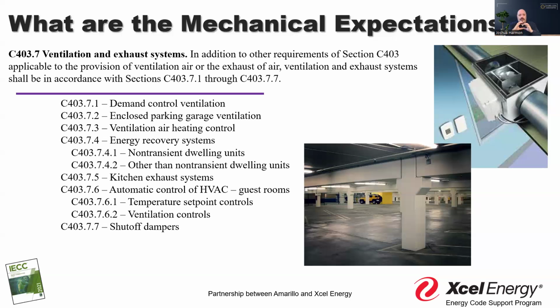But when it comes to the sewer or septic line, maybe 3 or 4 inches depending on the design, that's listed most of the time too. Yet when we talk about a 6-inch or 8-inch duct, everyone assumes we don't need to show where it goes - it'll just show up and get put in right. No - it's important we know from the beginning where this exhaust or ventilation system is going in the wall system, so a secondary trade doesn't block it and I can't route around the electrical or other lines. It's the biggest piece of equipment going through the wall system - we should know where it's going. Just throwing that out there.